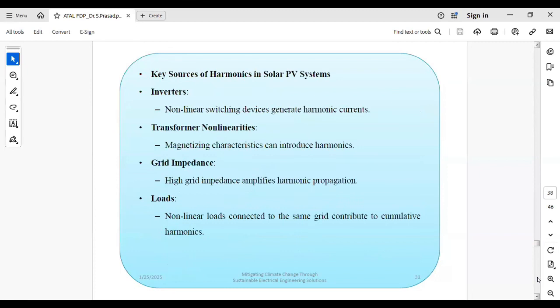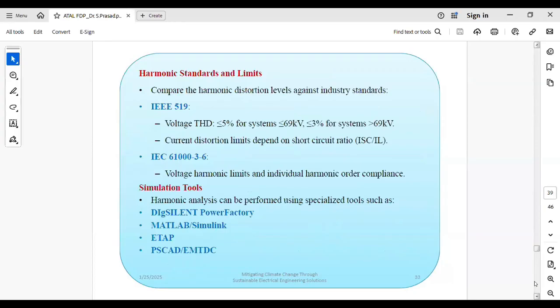Okay, and the key sources of the harmonics are inverters, transformers, nonlinearities, grid impedance, and loads. Basically, nonlinear loads will be available, due to which harmonics will be injected. These are the harmonic sources and the standards you have to follow. For software, use DIgSILENT PowerFactory, MATLAB, ETAP, PSCAD. At the industry level, we are using DIgSILENT, ETAP and PSCAD, an EMT simulation tool, to conduct the harmonic analysis.